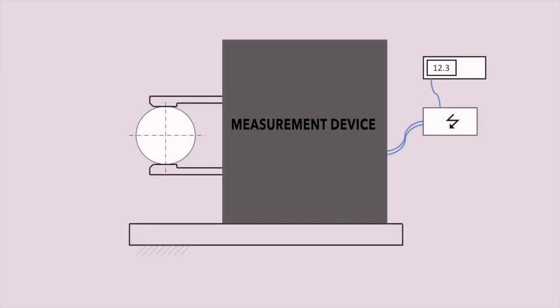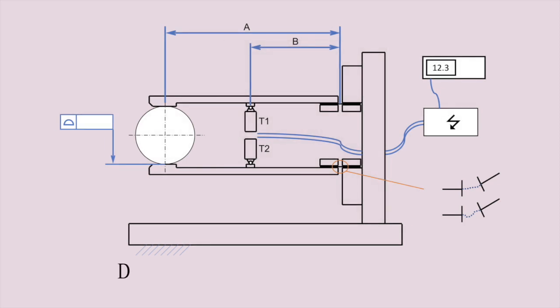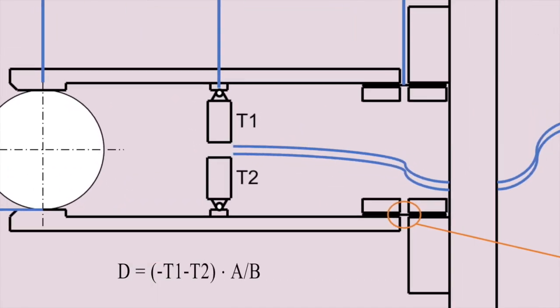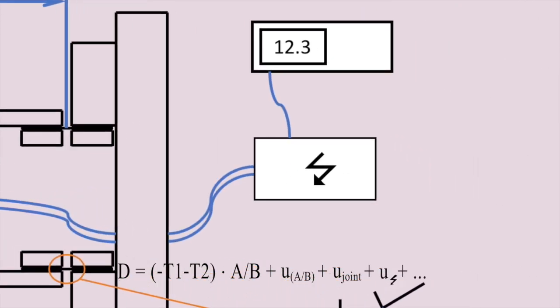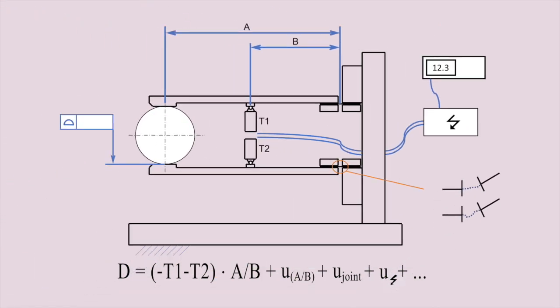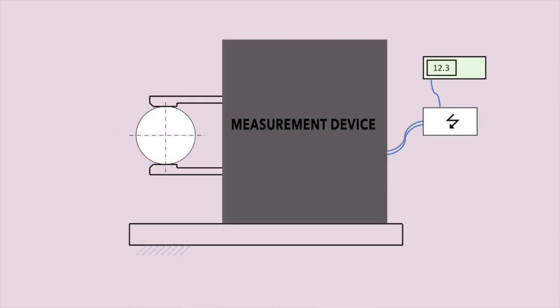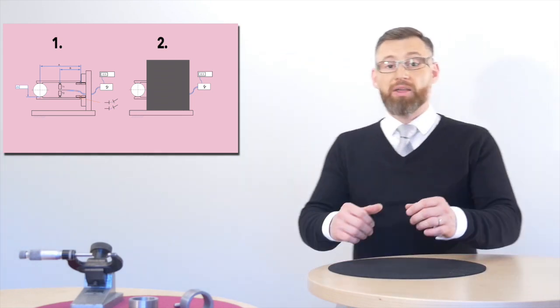There are two extreme approaches to finding the uncertainty. One I would call a bottom-up, where we would look inside the measuring device and all its relevant components, and we would build a multi-physical model of how the dimension of the measured part gets translated into the displayed measured value. The second one would be not to care at all about the guts and only observe the performance of the device at certain conditions. The proper approach is, as always, somewhere in the middle.